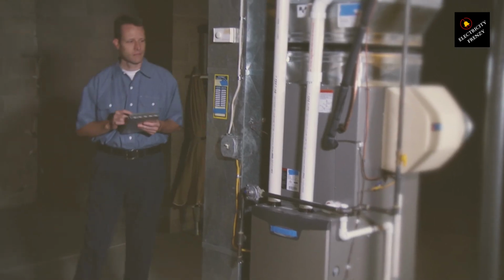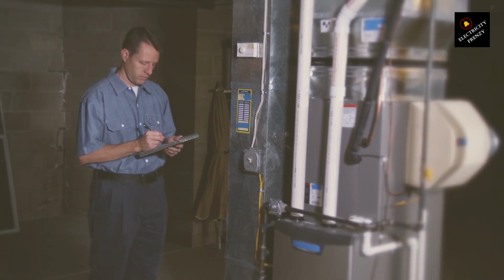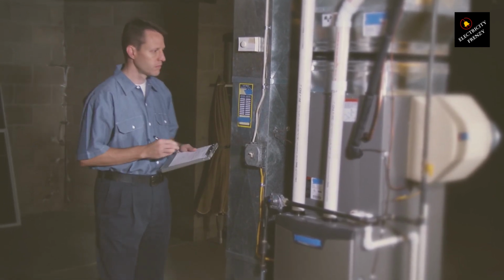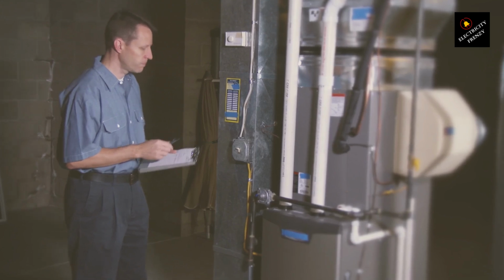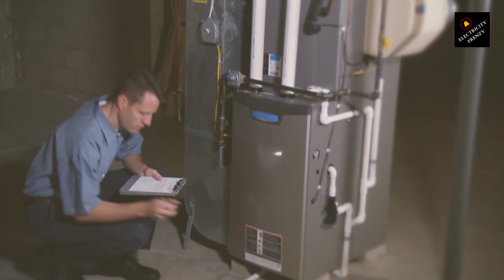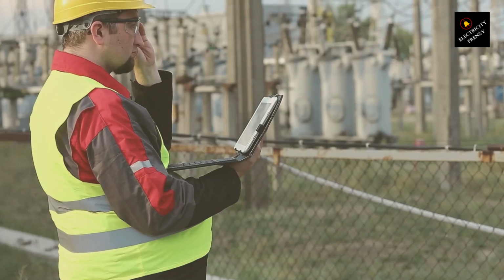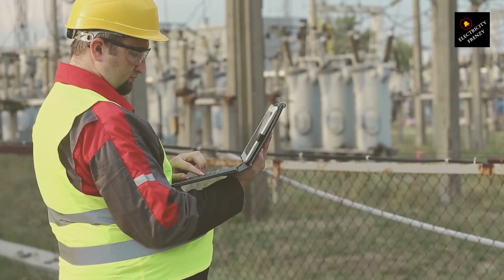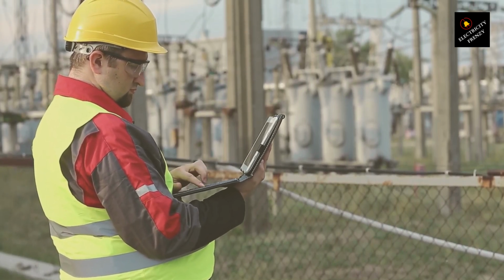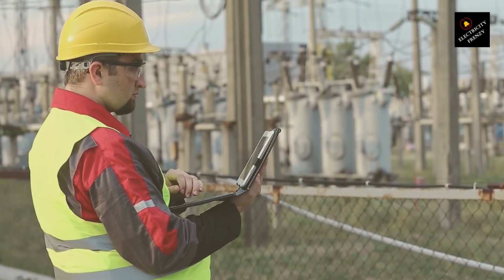You need your beats to align, and for that, you might need a frequency converter instead of a voltage transformer. A frequency converter does exactly what its name suggests: it converts the power supply frequency and voltage to match what your motor needs, ensuring it runs as intended, preserving its lifespan and efficiency.